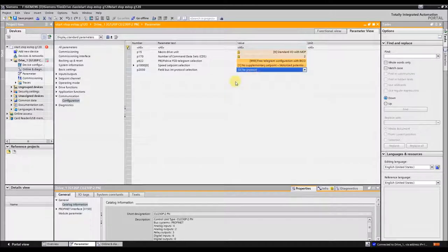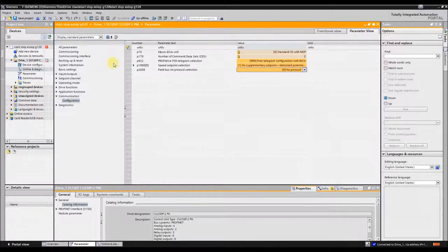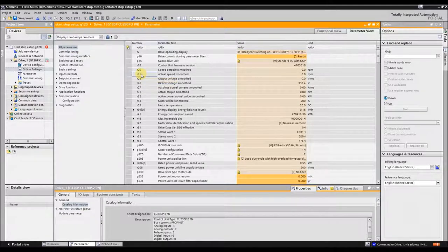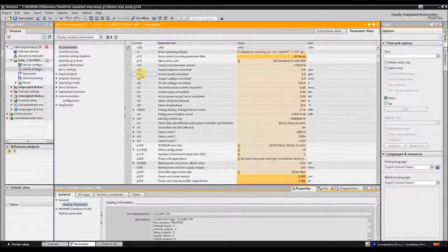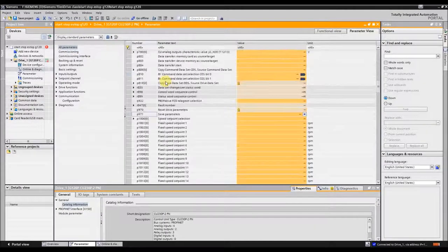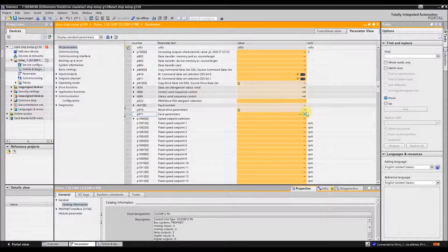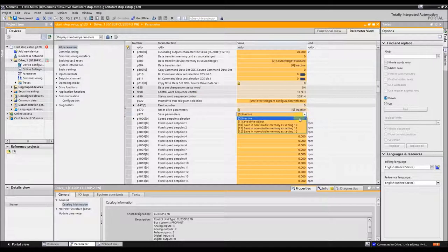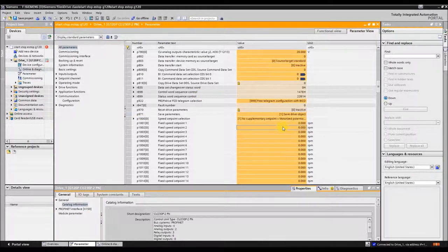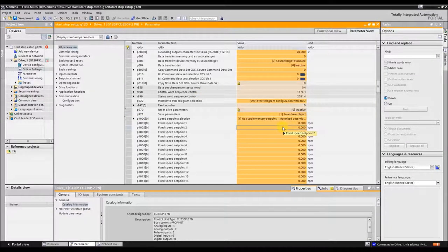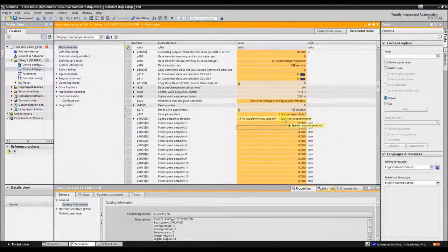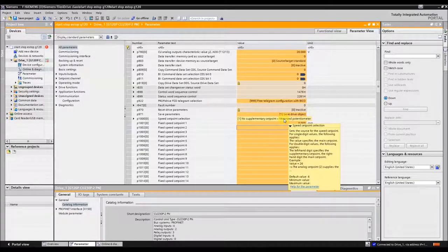Once you set it to no protocol, you need to do a RAM to ROM, which is parameter 971. That's what you would do on the controller. You need to set that to 1. Once you set that to 1, it'll do RAM to ROM, and then you need to restart the controller.